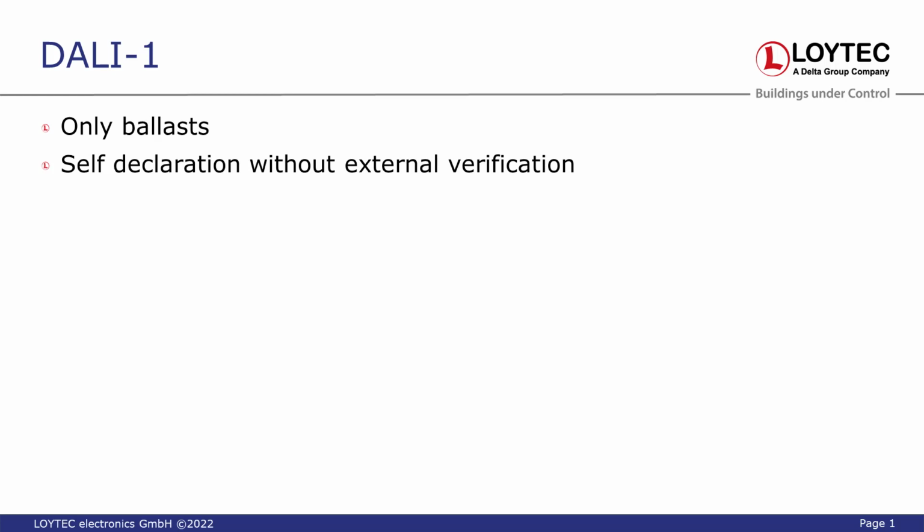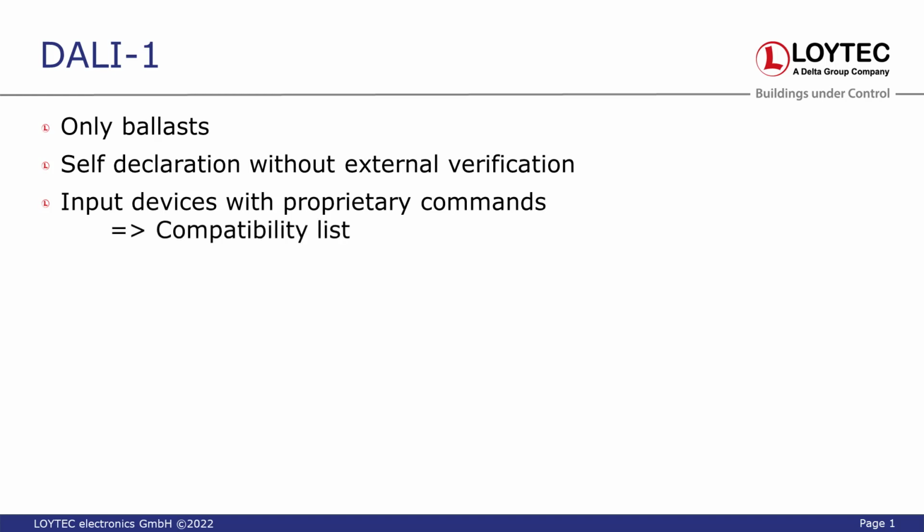Input devices, for example sensors or button models, were often using proprietary commands specified by the individual manufacturer. That meant that an input device may have to be implemented specifically. To have an overview of which DALI 1 device is compatible, LOYTEC keeps a DALI 1 compatibility list. All devices not mentioned on that list are not supported by our LDALI controllers.